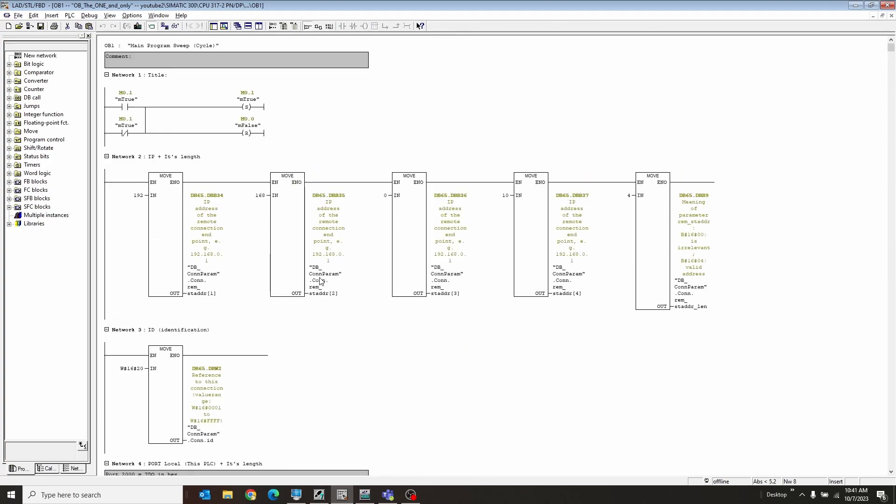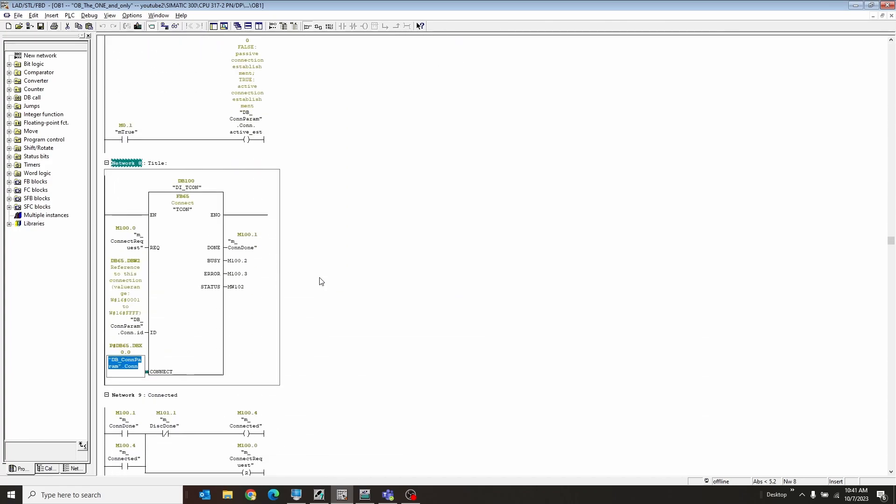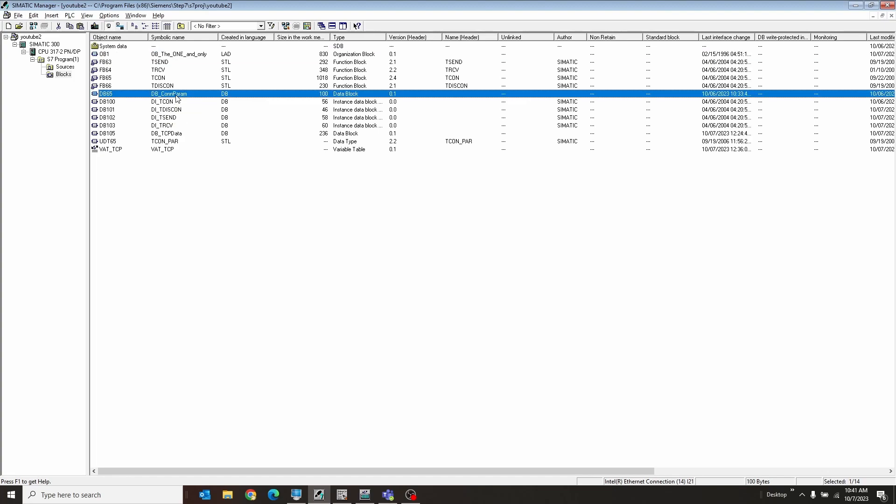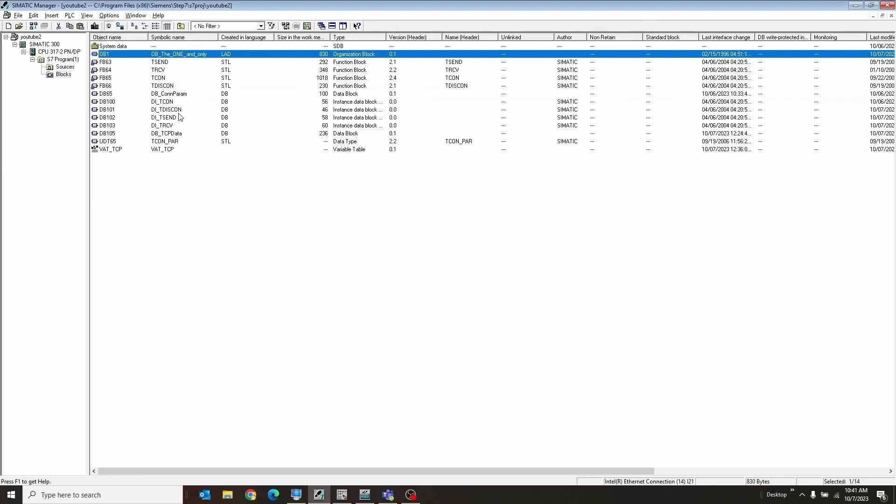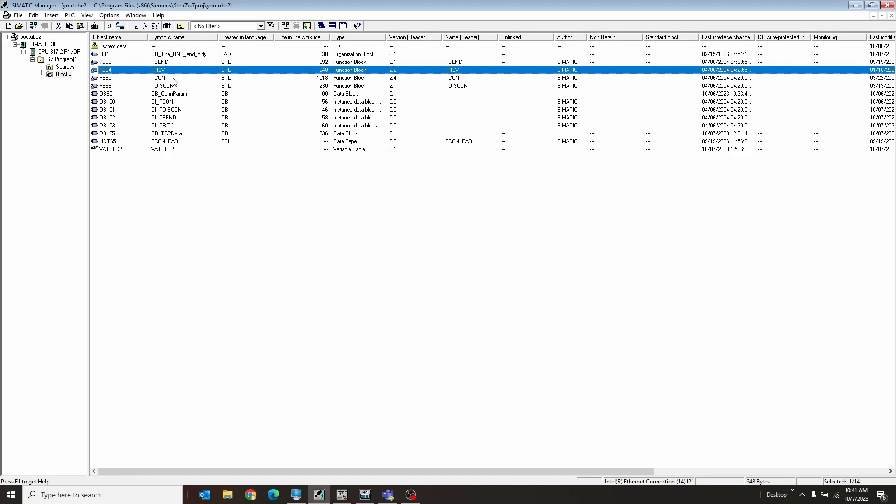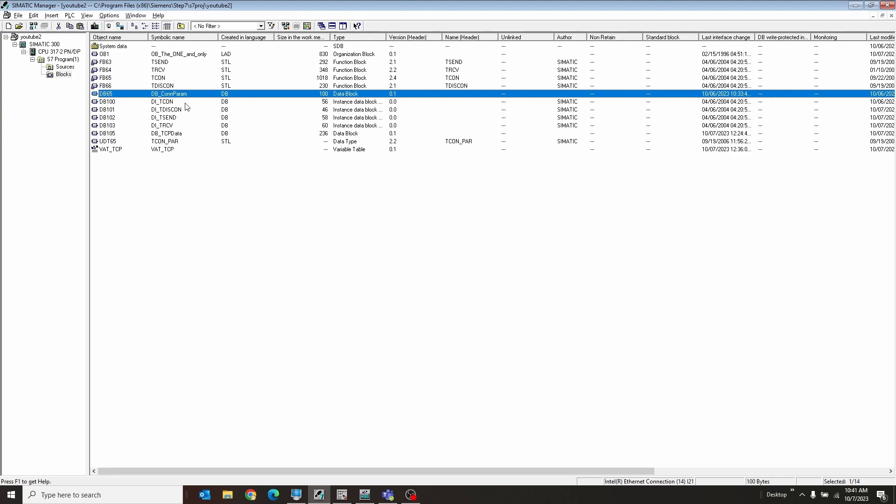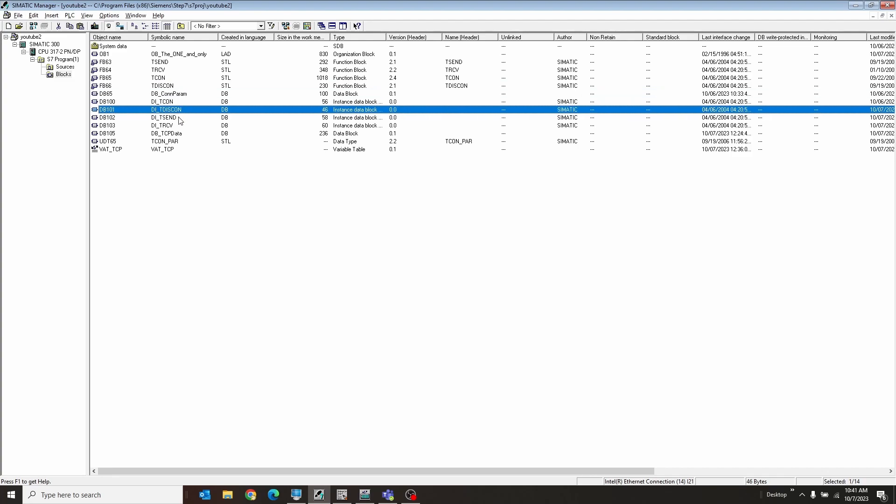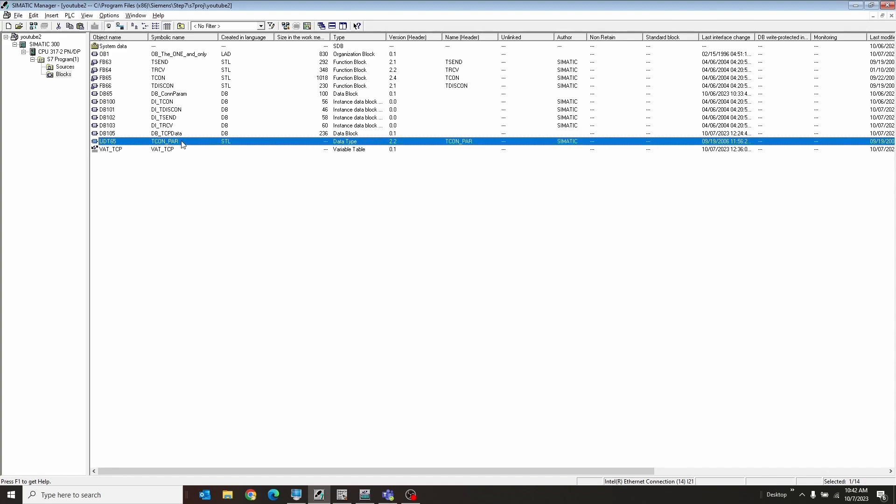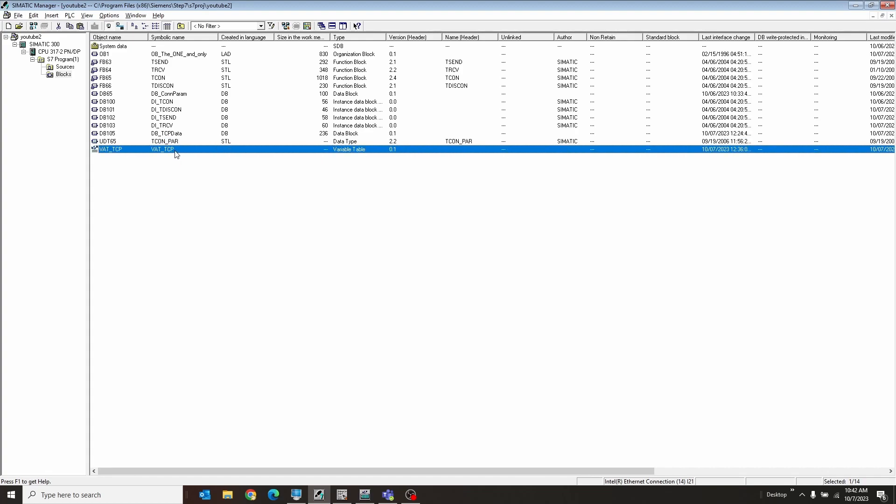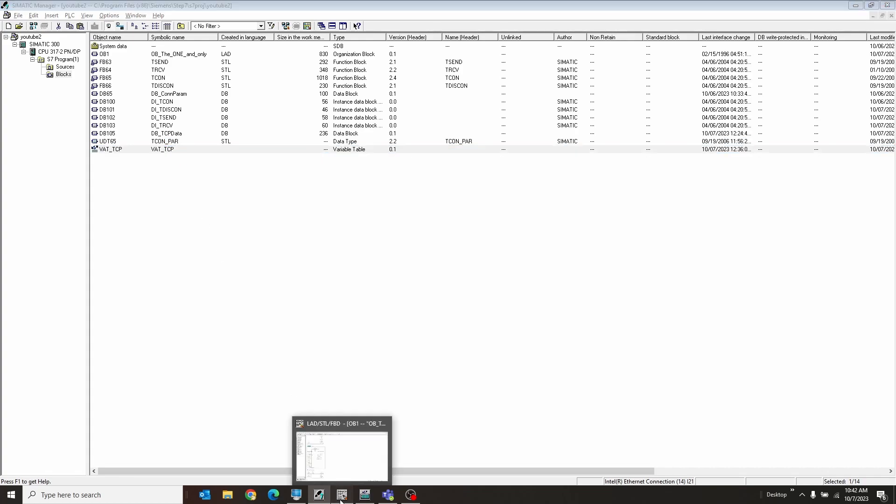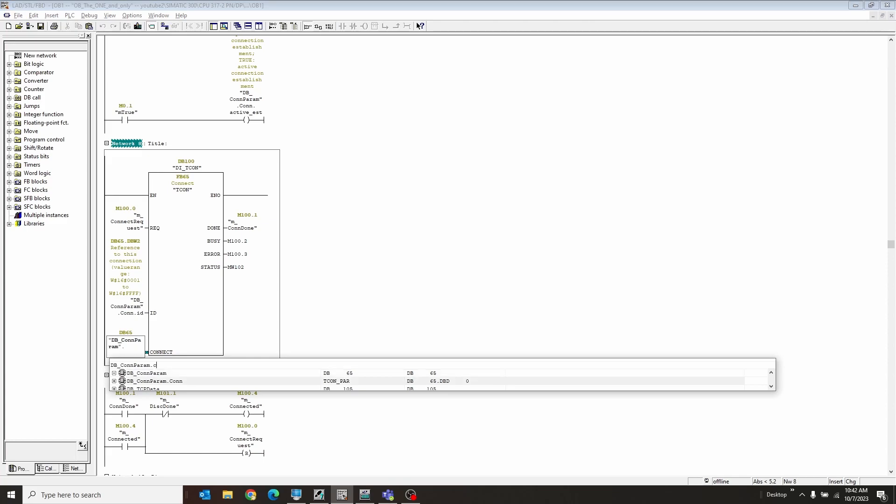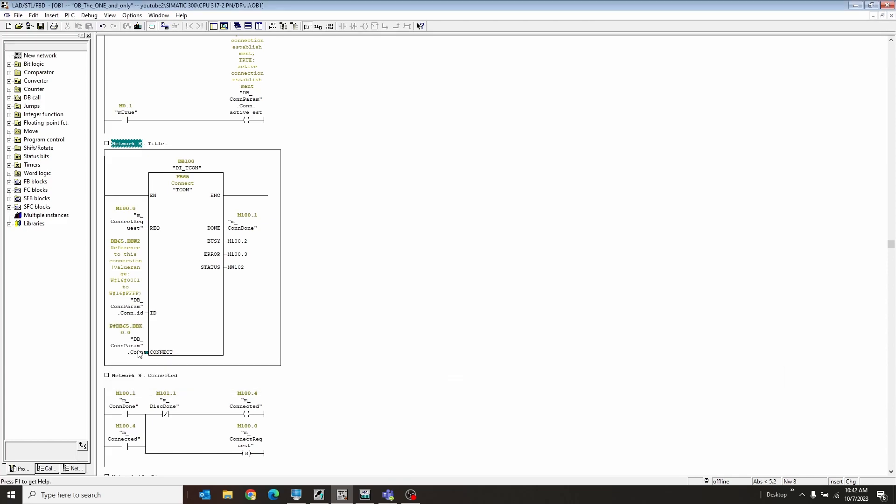And then these are the parameters that we're filling in. All this stuff up here goes into a database I've created called DB65_DBConParam. So you can see, by the way, since we're here, all the function blocks and databases that are used to create a TCP connection. There's T_SEND, T_RECEIVE, T_CON, T_DISCON, the connection parameters, and then the instance database for all those FBs. And then I have the data that I'm sending back and forth between the two PLCs. And then I have the UDT here that defines those parameters. And I have a variable table just for watching it. We'll get to that guy later. So anyways, this is the DB for the connection parameters right there. And then specifically drill down to the connection. You can put, like, that as an option, but it's not going to work. You have to drill down to the connection part itself.